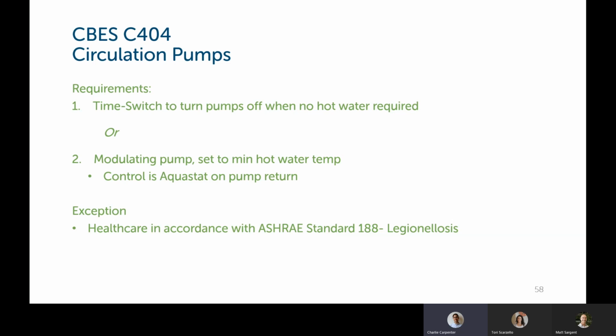Next slide. For circulation pumps on the hot water system, you need to have either a time switch that turns the pump off when there's no hot water required in the building, usually based on occupancy. If it's say a business or an office hour type of building, you'd turn the pumps off when no one's in there, or have a modulating pump set to an aquastat to control the pump based on the pump return water temperature. So if there's not a lot of hot water demand, then the pump will slow down, or if there's a lot of hot water being used, then the pump's going to speed up to circulate more water.